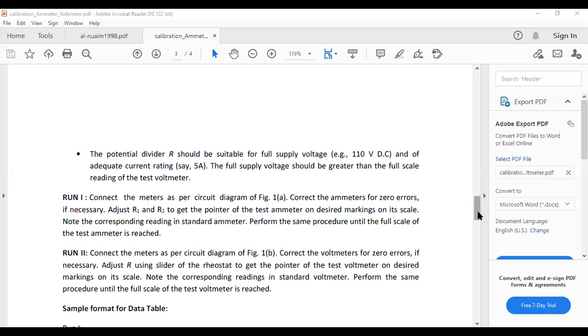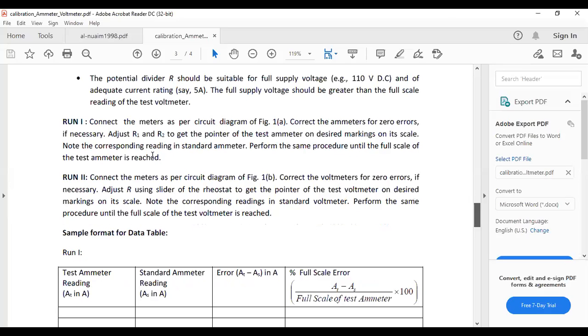Next, we'll go back to the report part. So this is the run one where we do the ammeter calibration, and in run two we have the voltmeter calibration. So in ammeter calibration, as we have seen, generally the test ammeter has less range compared to the standard ammeter. Suppose we want to calibrate 1 to 5 ampere. For each discrete ammeter reading, first we'll set that ammeter reading at the test ammeter, then we'll check how much we are getting from the standard one, then we calculate the error.